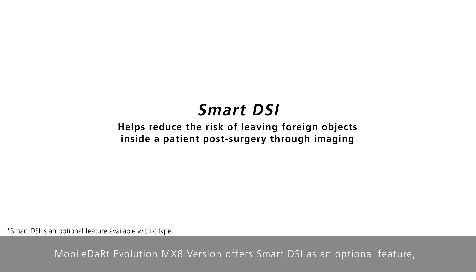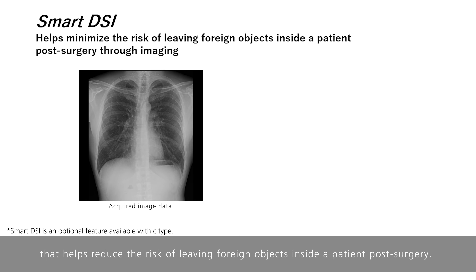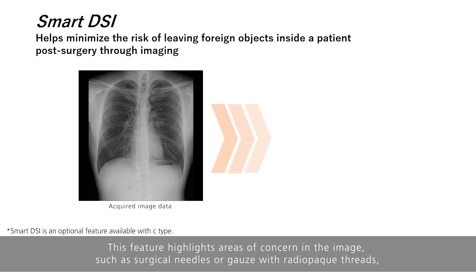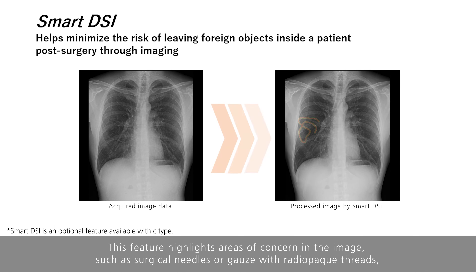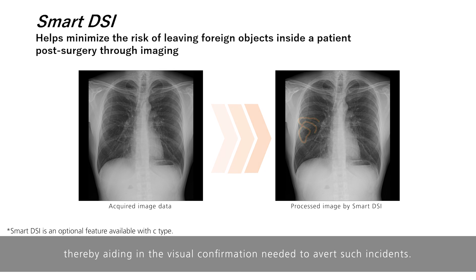MobileDart Evolution MX-8 offers Smart DSI as an optional feature that helps reduce the risk of leaving foreign objects inside a patient post-surgery. This feature highlights areas of concern in the image, such as surgical needles or gauze with radiopaque threads, thereby aiding in the visual confirmation needed to avert such incidents.